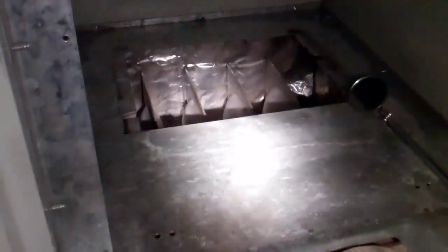I wasn't expecting any, but as long as you got it opened up I think it's a good idea to just look in there and check. I did have one, my shop heater actually developed a crack in these, in one of these combustion areas and had to replace it because there's essentially no repair for that. So I like to look at them when I get it opened up.